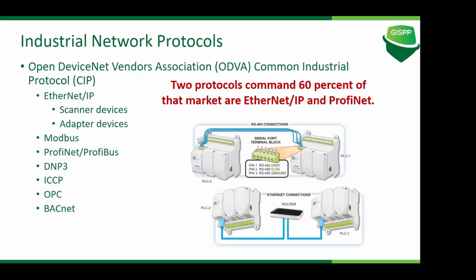Now, industrial network protocols: there's an association called the Open DeviceNet Vendors Association. They are the responsible body for making common industrial protocols, called CIPs. The listed ones include Ethernet/IP — here IP does not mean Internet Protocol, it means industrial protocol. It has two modes, one for scanner devices and one for adapter devices; we will see the difference between them. We'll also talk about Modbus, Profinet, Profibus, DNP3, ICCP, OPC, and BACnet.